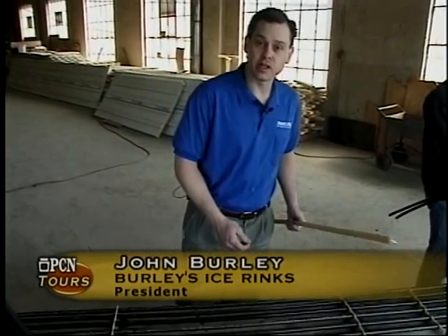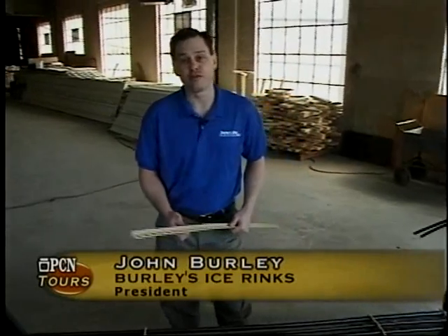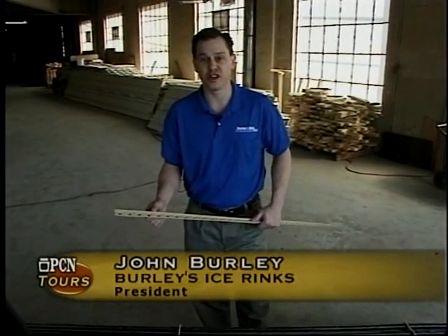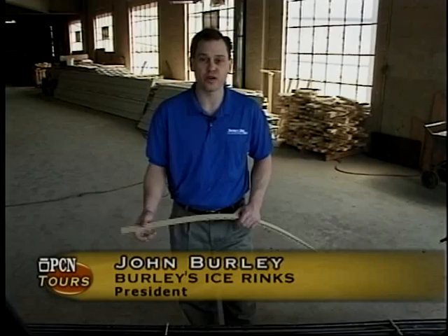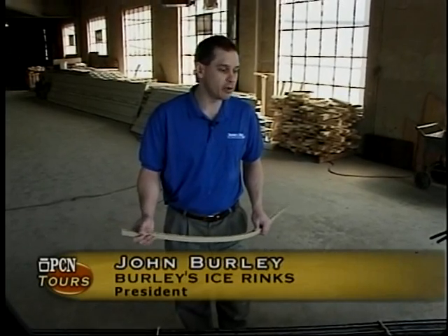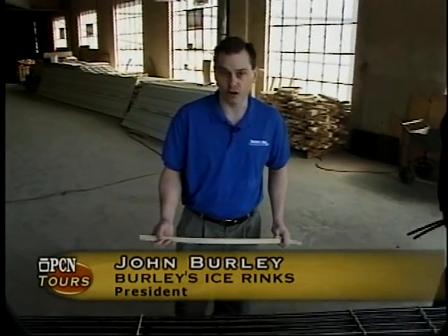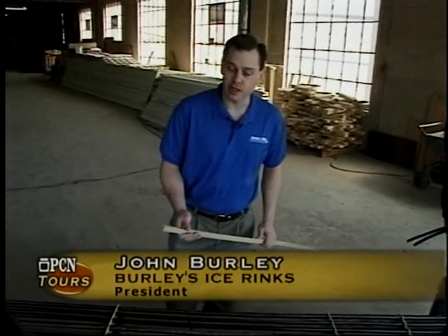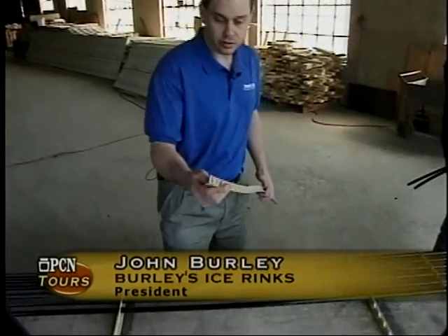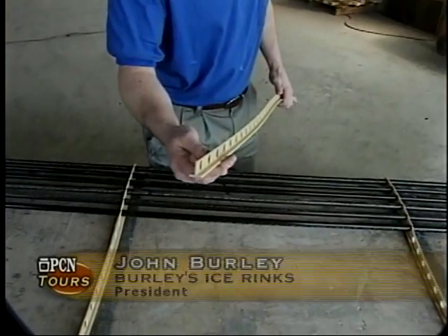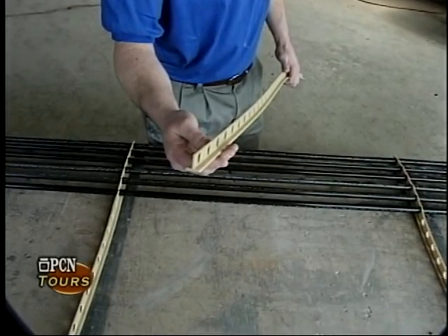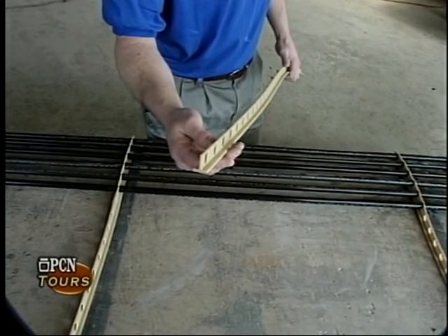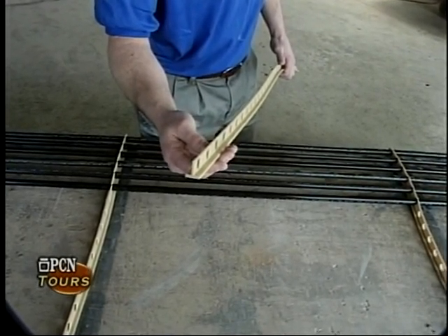The piping system consists of literally 26 miles of tubing that's contained underneath the ice sheet for heat transfer. It's 22,000 square feet of surface area, and it's designed to maintain the ice sheet between 15 and 20 degrees. In making up the piping system, we're using an extruded spacer strip to make up what we call our Porta-Pipe and our Perma-Pipe rink piping systems. These are both for permanent and for portable applications for the ice shows.